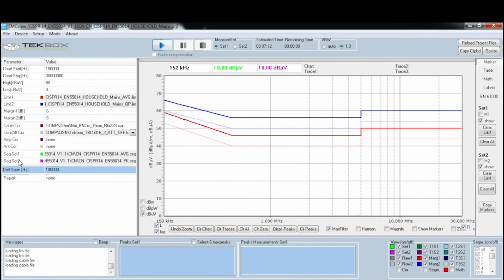We have segment set 1 and segment set 2. Set 1 is going to do a scan based on the average scan, and segment set 2 is based on the peak scan. You can see set 1 is now selected. If I click start now, the software will tell the spectrum analyzer to start an average scan. Once that is done, I can select set 2 and start it again, and the result will show here as well with the peak scan. Those are the most important parameters to set for this test. So we set it just as it is, and put it back to set 1.